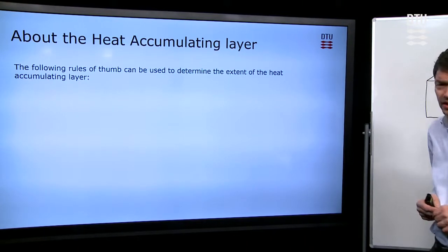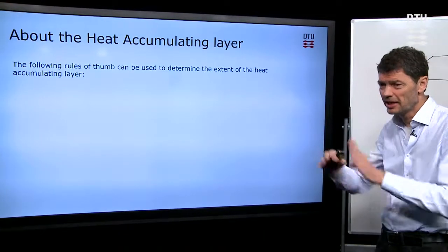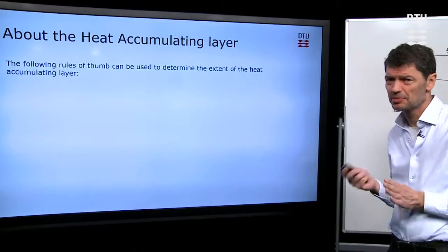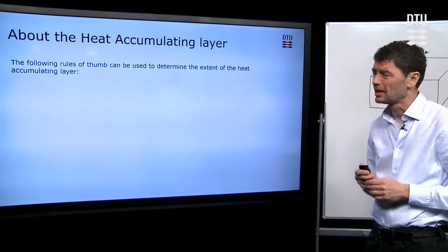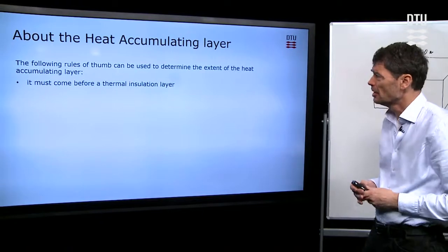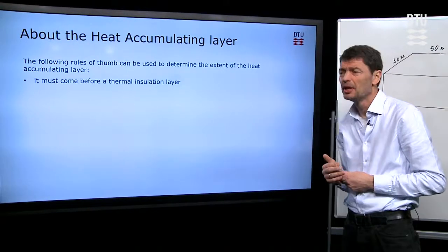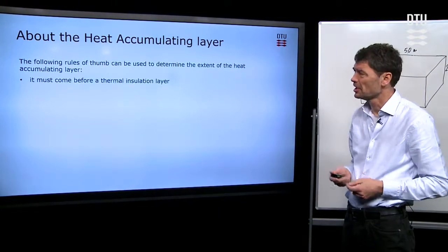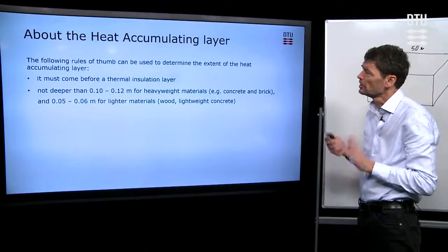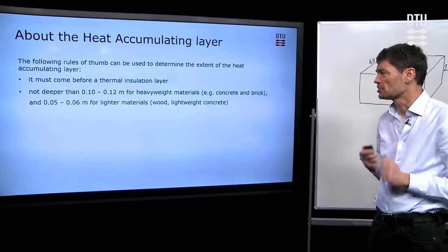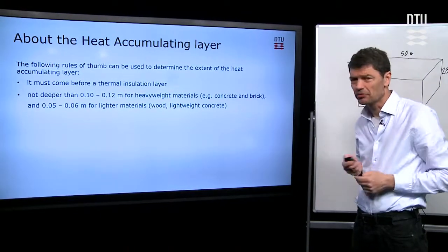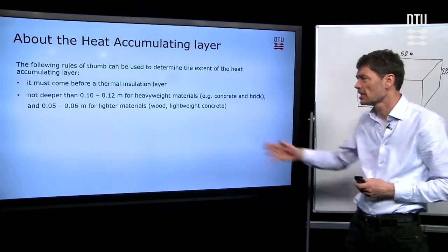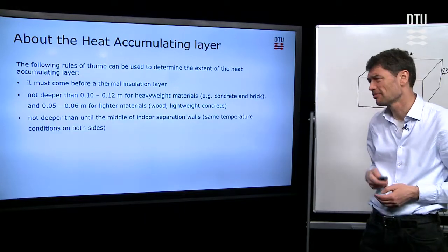I'll just have a few words to say on that heat accumulating layer, so how much material we can consider in our calculation. Because there are a few rules of thumb of how much material really interacts with the air that we have in the room. If you have a multi-layered structure, then we should consider only the layers that come before possibly also an insulation layer. Also, normally, if we have heavyweight, normally building materials, we don't see thicknesses larger than around 10 to 12 centimeters. Also, depending on how well-conducting the materials are. For some lighter materials, we'll probably see slightly less, five to six centimeters.